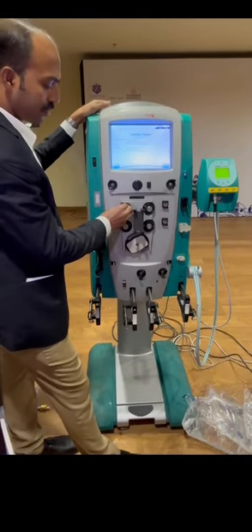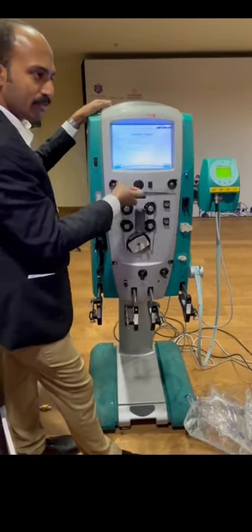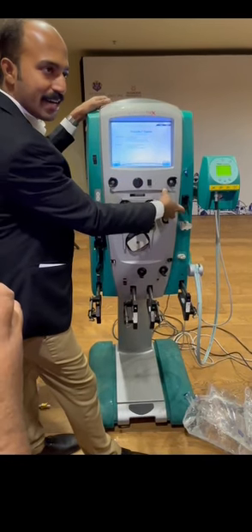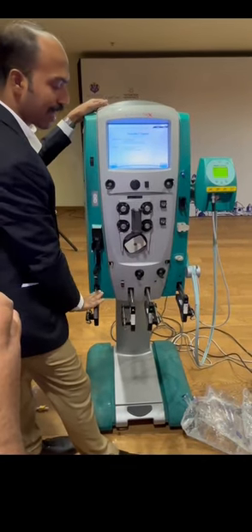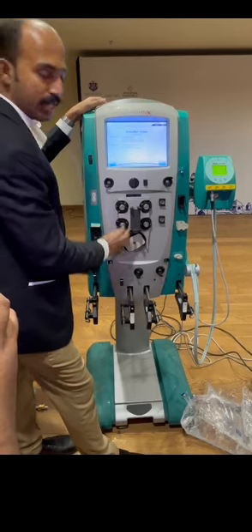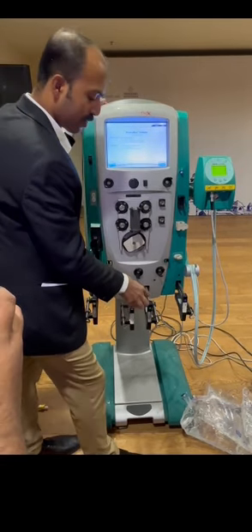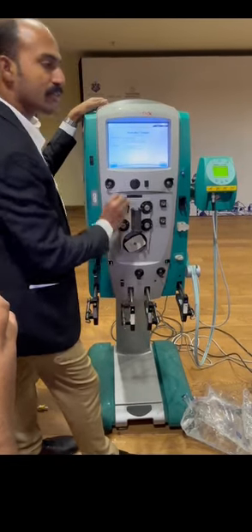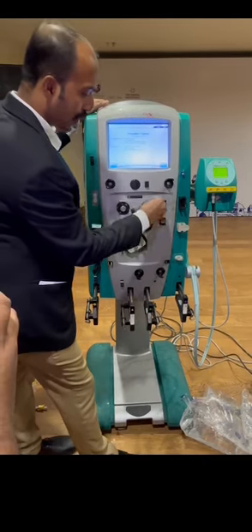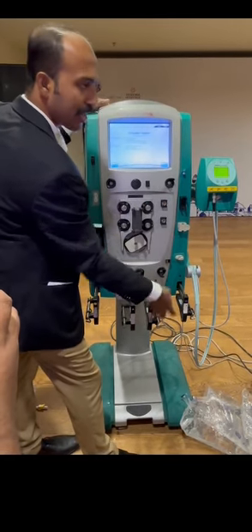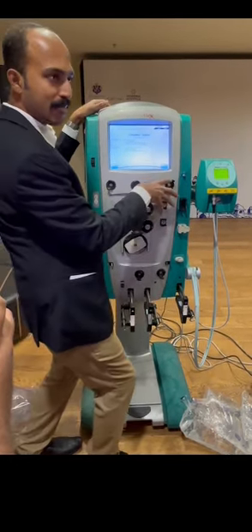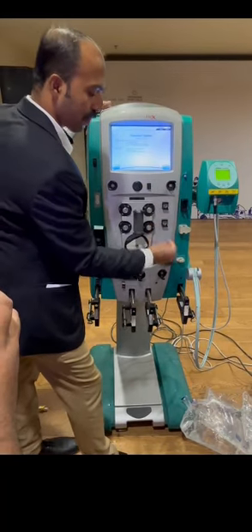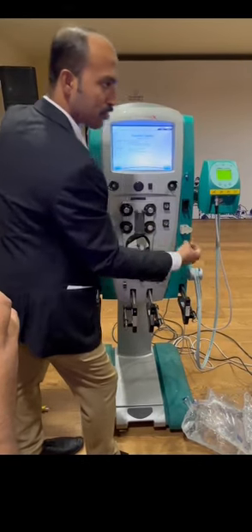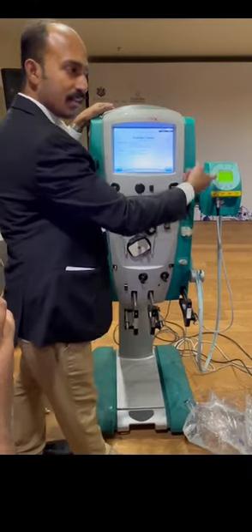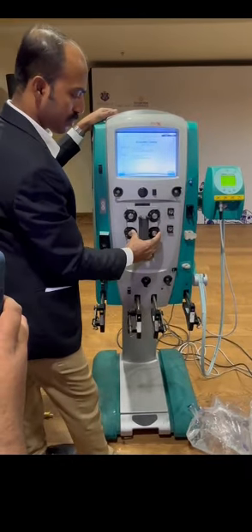Okay. So this is for the effluent, to drag the effluent from the filter or from the dialysate compartment to the drain bag. Then this is for the pre-replacement or the citrate, to take from here and to deliver before the filter. And this is for the dialysate, to collect the dialysate and give it to the dialysate compartment. This is for the post replacement, which will collect the post replacement and give it to after the filter. Okay, these 4 pumps.